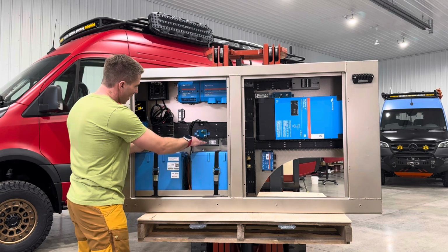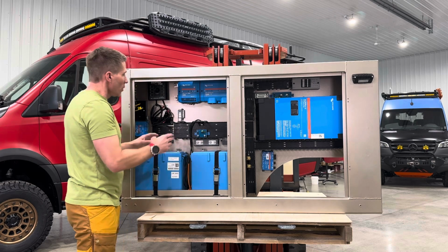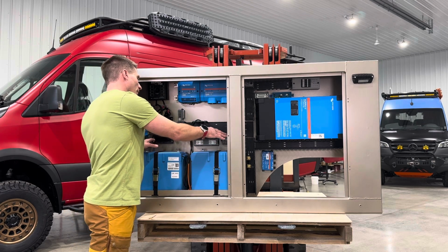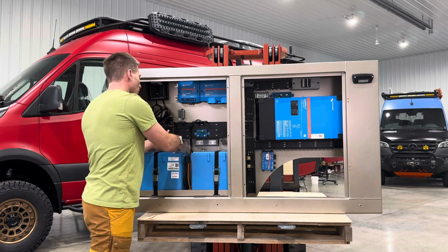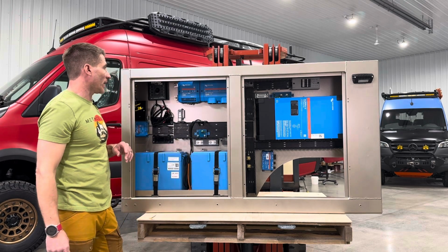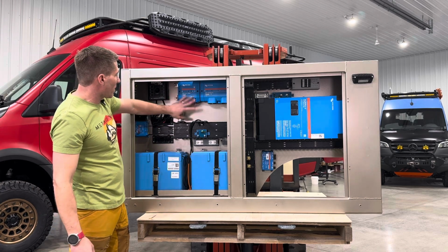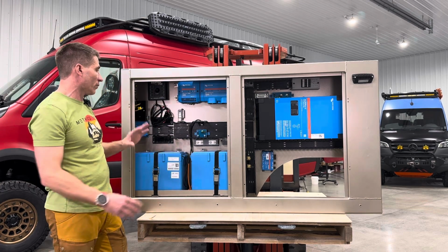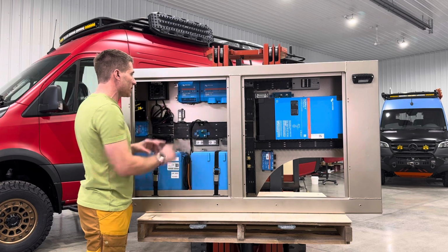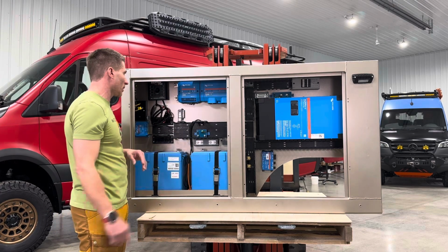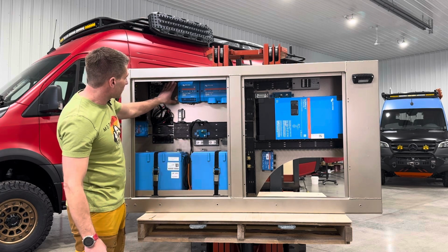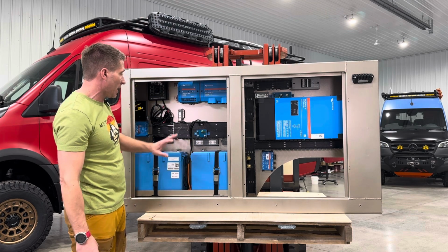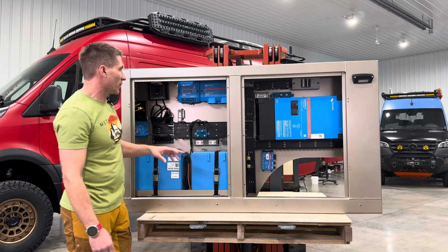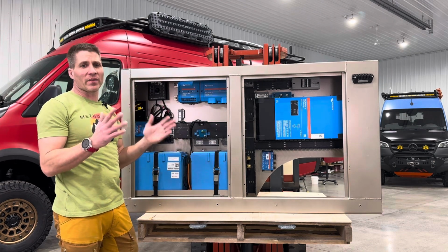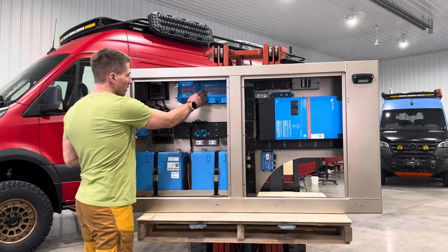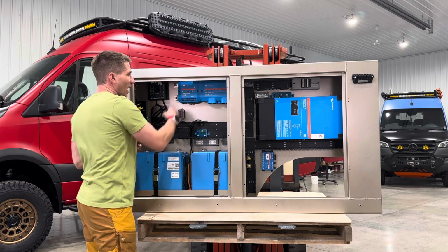Our negatives then tie up to the negative. Both are connected into our Lynx Smart BMS, which is an intelligent piece that monitors the batteries. The batteries are connected to the Smart BMS, as well as other things. Power comes into the Smart BMS, which is the brains of our unit. That's then attached to a Lynx distributor, basically a bus bar with the ability for fuses, and it communicates to the Lynx through a data cable.